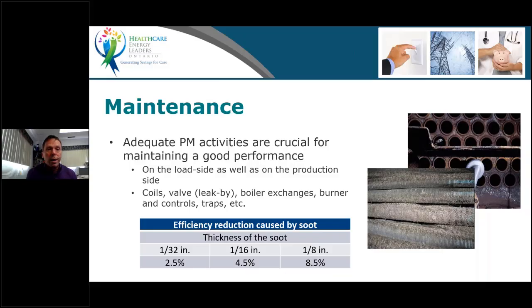Maintenance is very critical for proper efficiency of the boiler. When we say maintenance, we're always talking heat exchanger. A coil is a heat exchanger. Inside the boiler is a heat exchanger. Both sides of those heat exchangers need to be maintained. Like you see here on those coils, those look like steam tubes in a heat exchanger. They're really fouled. They need to be cleaned. You're going to lose a lot of efficiency or effectiveness through that heat exchanger if you don't maintain it properly. You also have to be careful how it's maintained. Those are fairly rigid fins, but some of them are more delicate, so you don't want to squish all those fins. And obviously, if it's that dirty, something happened to the filter, so it's a whole system that you have to maintain properly.